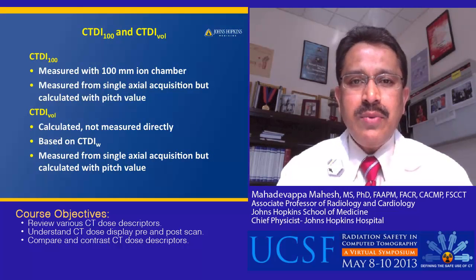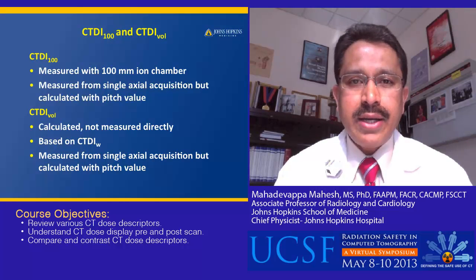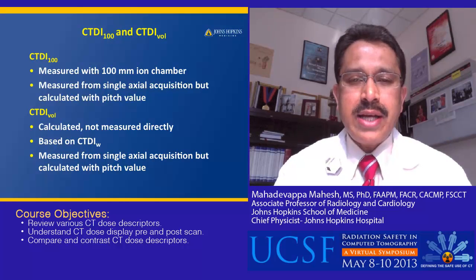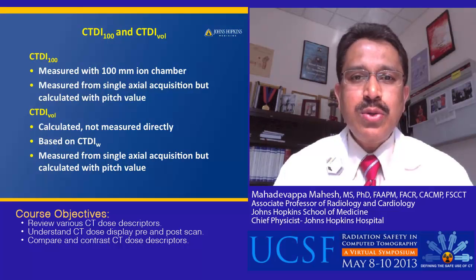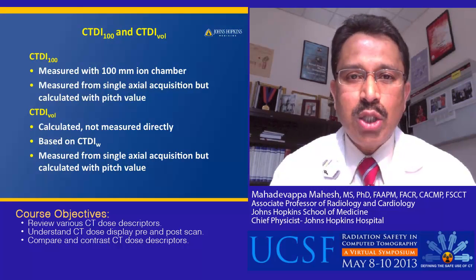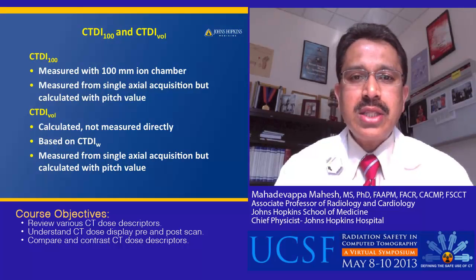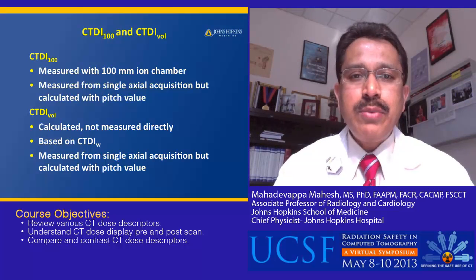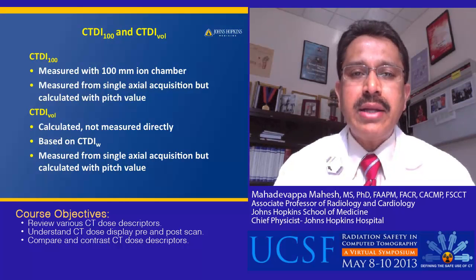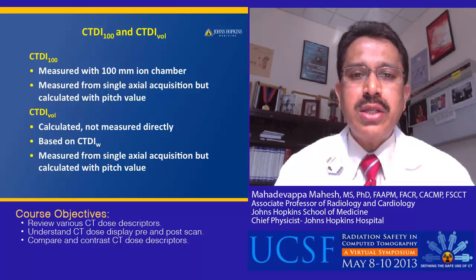Commonly we measure CTDI using a 100 mm ion chamber, noted as CTDI100. It is used in standard phantoms to measure the dose index number, or the scanner output, both at the center and at the periphery. From this measurement, we calculate CTDIvol, which is not a direct measurement on the patient but a measurement done on the phantom.